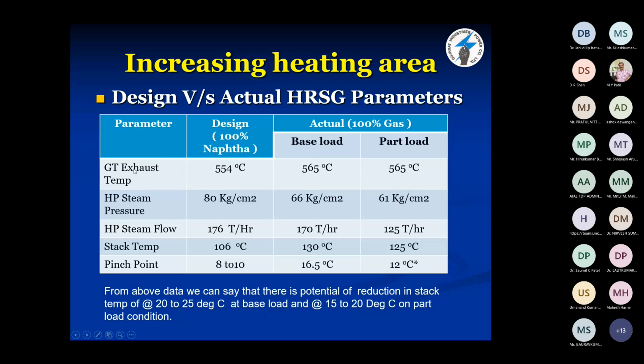You can see that GT exhaust temperature, the HRSG was designed with 100% naphtha. At the time when the plant was commissioned, the naphtha was available as a fuel. With passage of time, the naphtha was totally obsoleted. It was not economically viable. So we have taken the machine at 100% gas. Now it is operating at 100% gas.